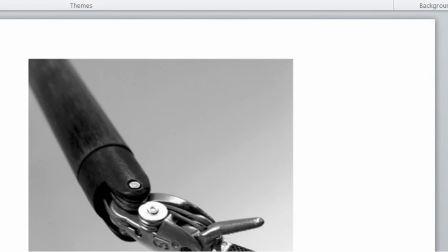One of the well-known force sensing devices that apply this sensing principle is the LVDT-based force transducer. As the name implies, the transducers make use of an LVDT to perform force measurement. With regard to this, the LVDT core is usually coupled with a linear elastic element, where the force is applied and causes the elastic element to deform. The position of the LVDT core will change, allowing an analog signal to be generated in proportion to the applied force. This sensing scheme is capable of providing accurate measurements and can even resolve millinewton force.